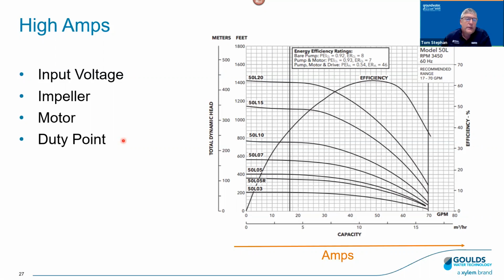The last one is duty point, and duty point just means that maybe we're operating to the right of the curve, right? High flows. With a centrifugal pump, at high flows you're going to see higher amperage compared to the amperage measured at lower flows. So maybe something has changed in the system and the TDH, or total dynamic head, has been reduced. Pumping levels change and all that. And we're operating maybe farther to the right than we were in the past.